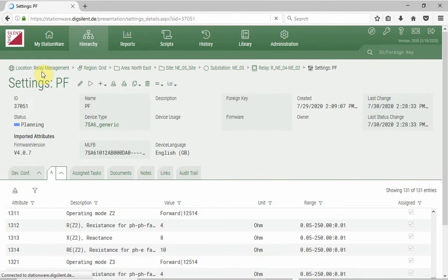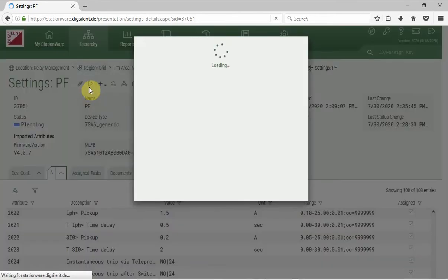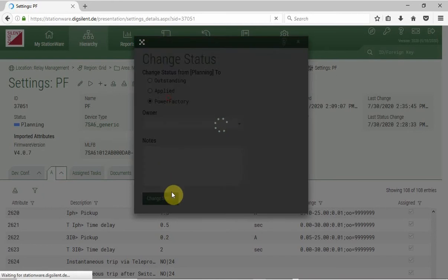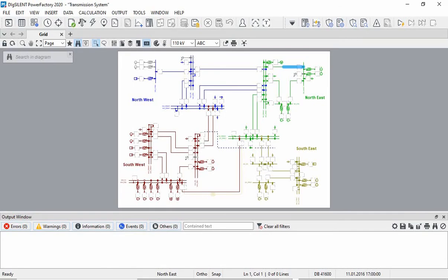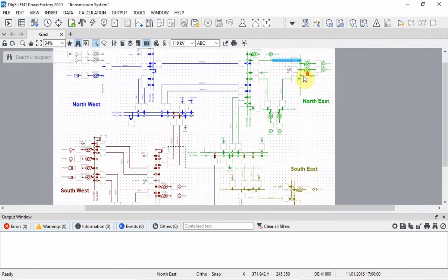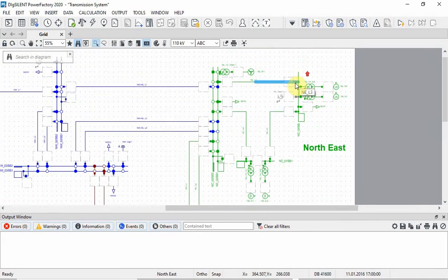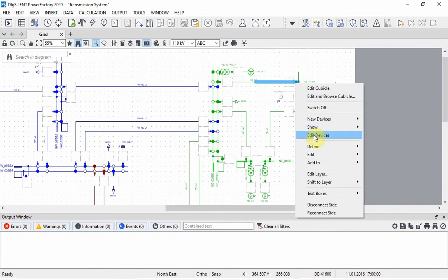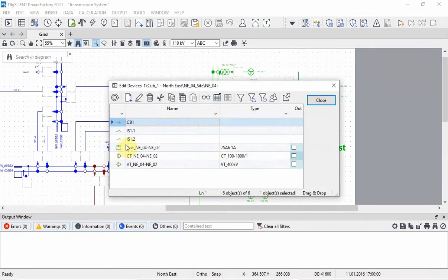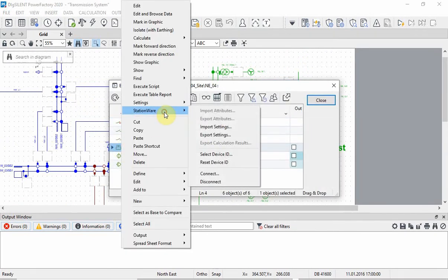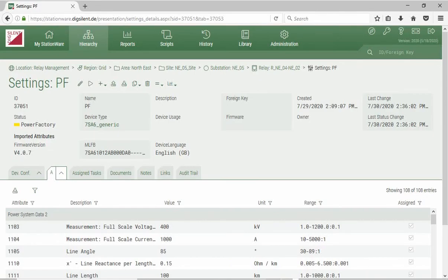In order to verify these settings, we will import them into the corresponding protection device representation in PowerFactory. For that, we will change the status of the settings file from 'Planning' to 'PowerFactory'. Open PowerFactory and navigate to the protection device of interest. Connect PowerFactory and Stationware by inputting the service endpoint and user credentials.